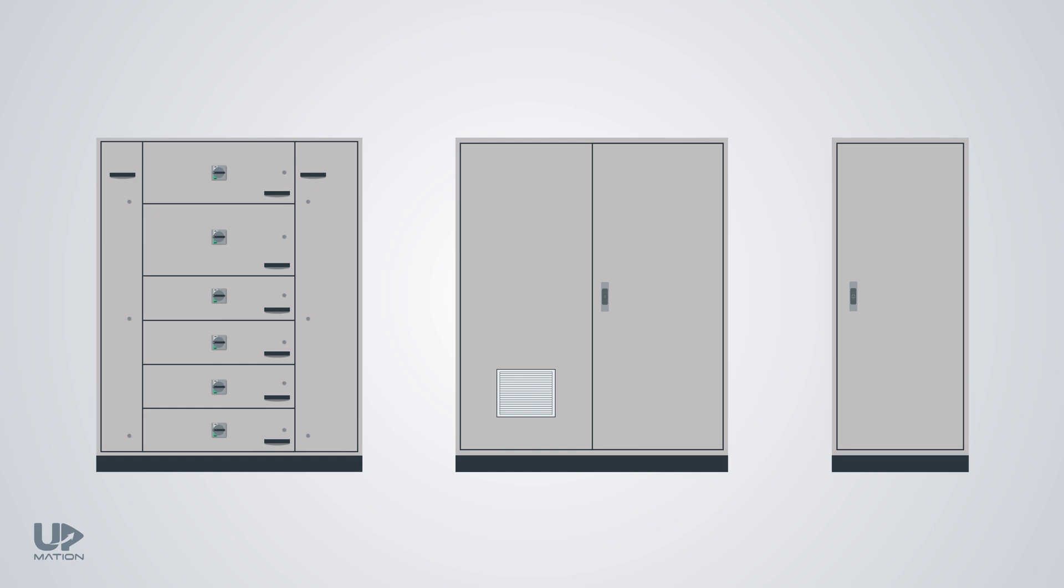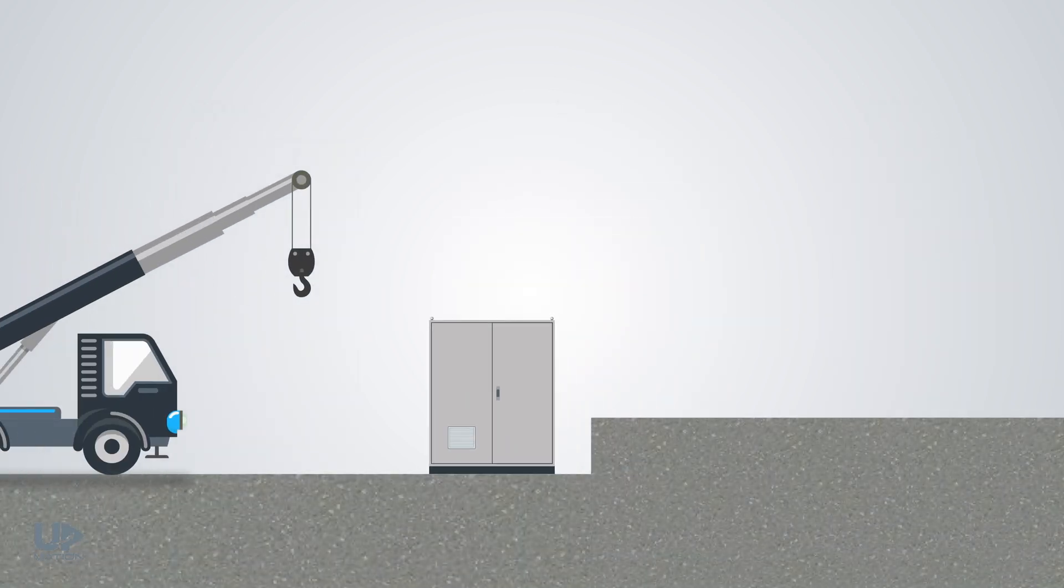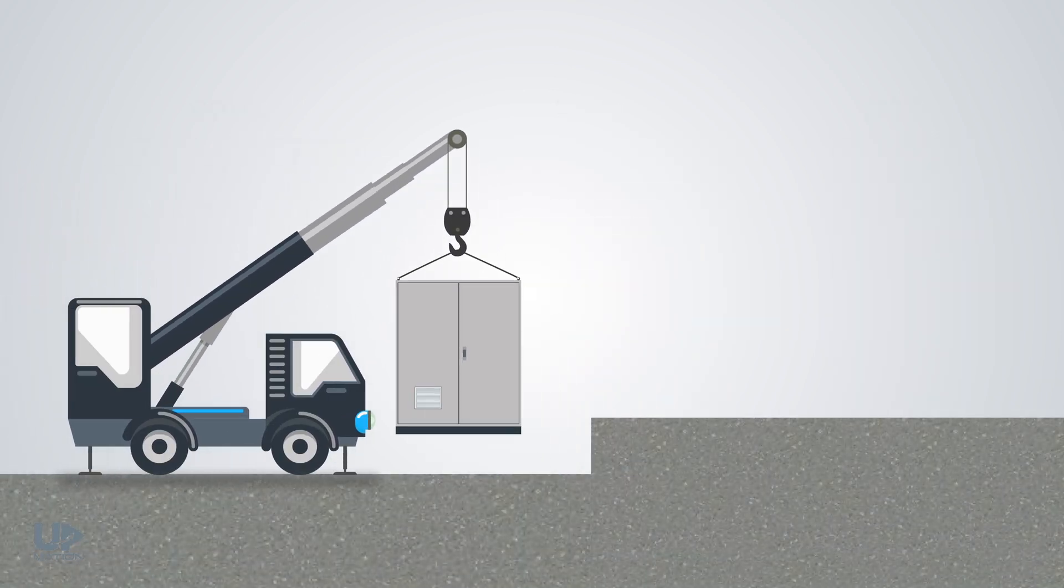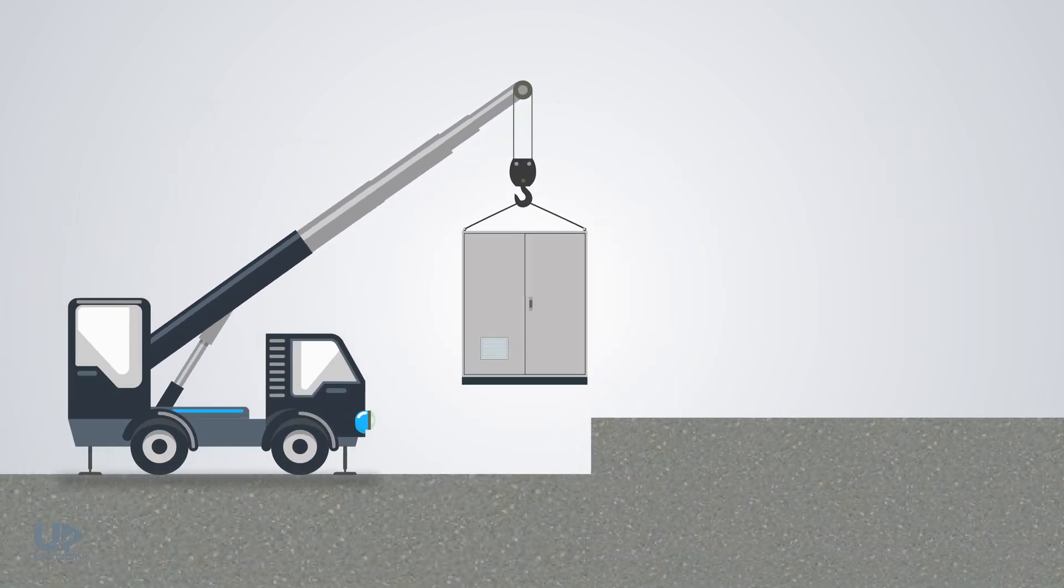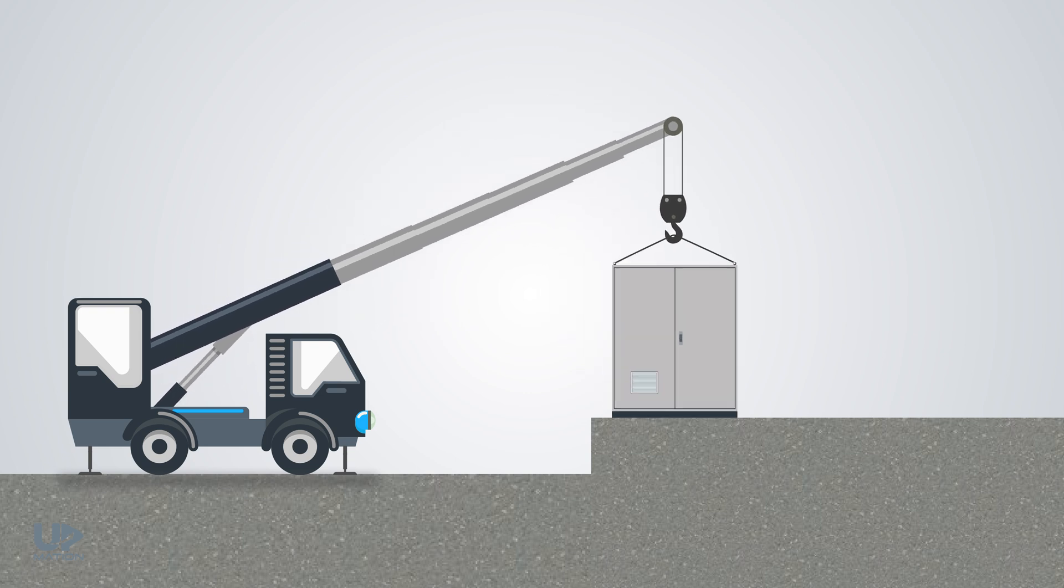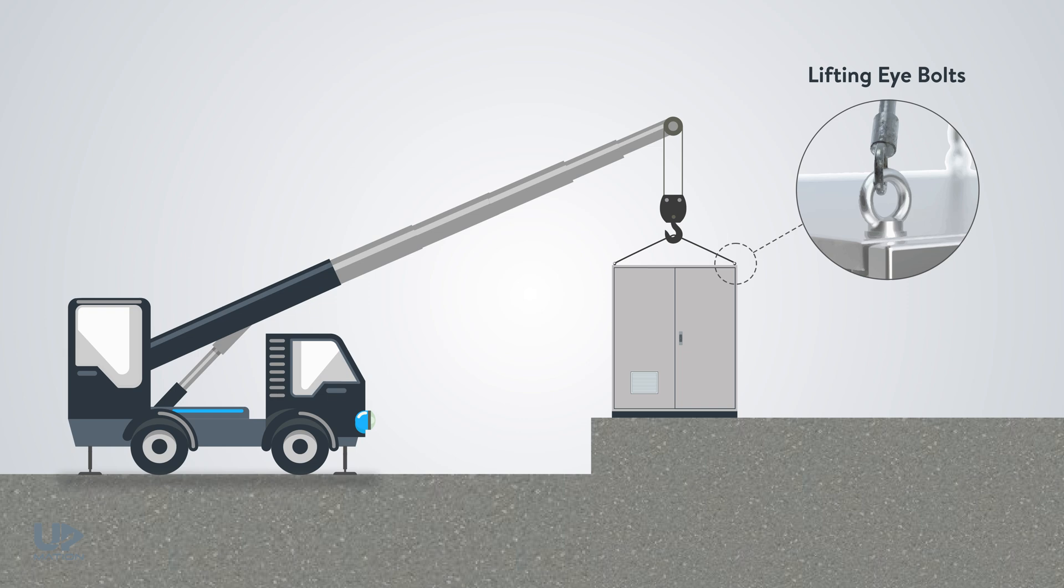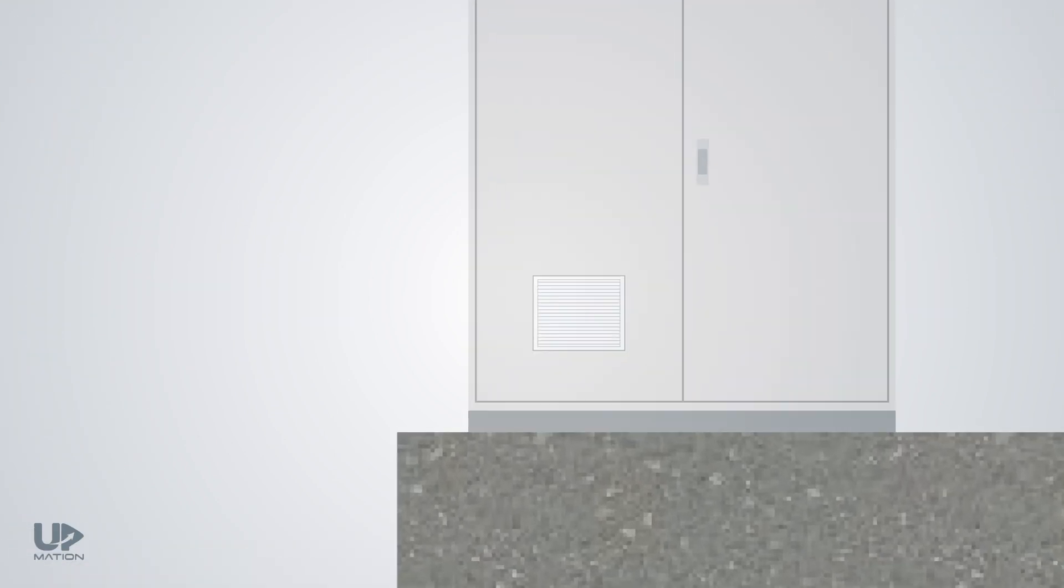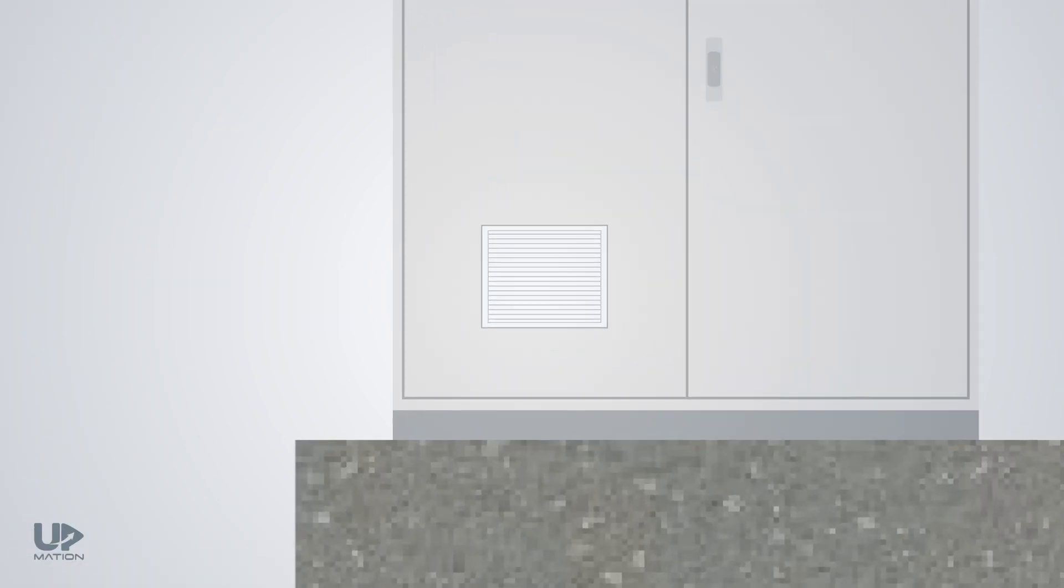As all of the electrical panels have a metal enclosure accommodating many electrical and non-electrical devices, they are pretty heavy most of the time. Therefore, to lift, move or install them using a crane, the enclosure manufacturers consider lifting eyebolts directly on top of the frame corners. After the placement of the panel in its final position, we should fix them in there by bolting their bottom frames to the ground.